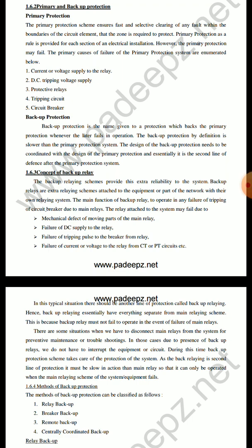Primary protection means the current and voltage are supplied to the relay. We have varieties of relays, but we need to protect through the current and voltage supply to that relay. In case of a fault, the relay will signal the circuit breaker, and the circuit breaker will disconnect the entire supply. Then there is the direct current tripping voltage supply, protective relays, and tripping circuits. Tripping circuits and circuit breakers are the same, but there are some variations based on utilization. Backup protections are needed in case the main protection setup gets a fault or error. The backup protection will save the entire setup.